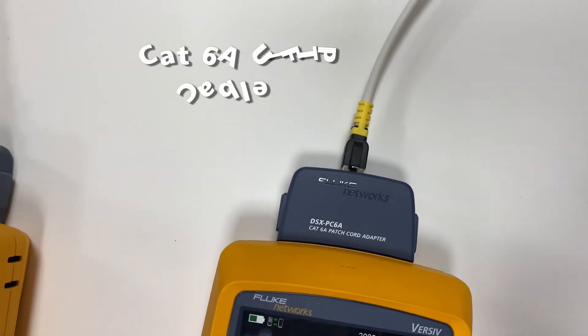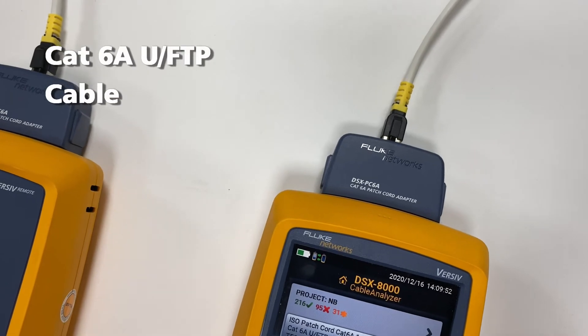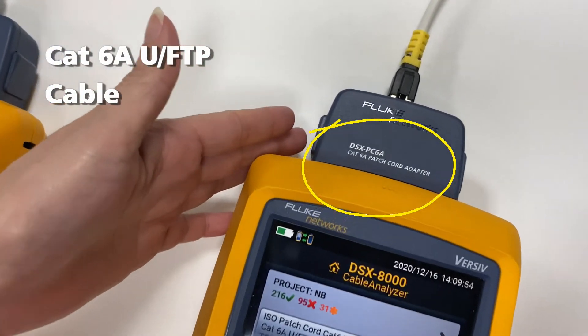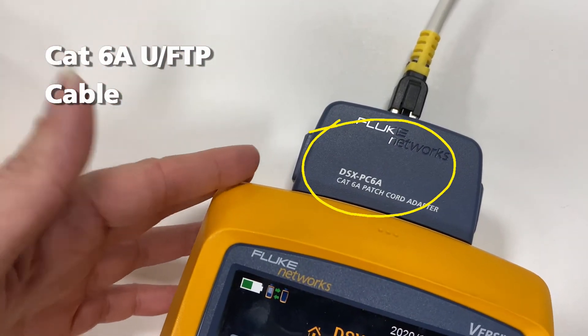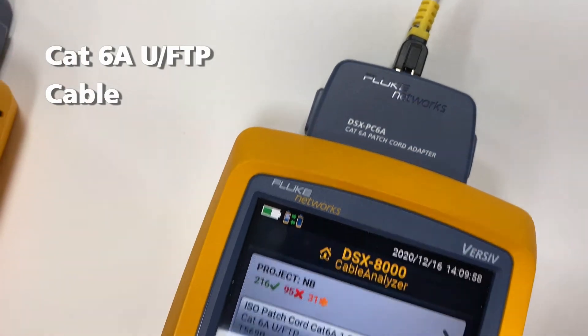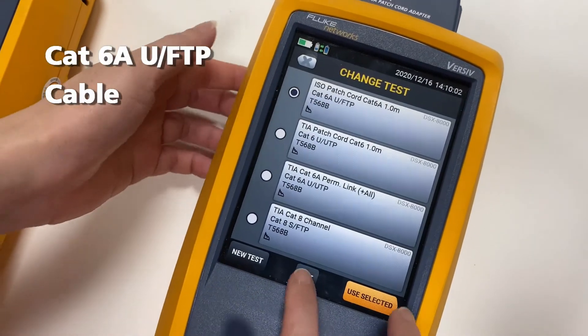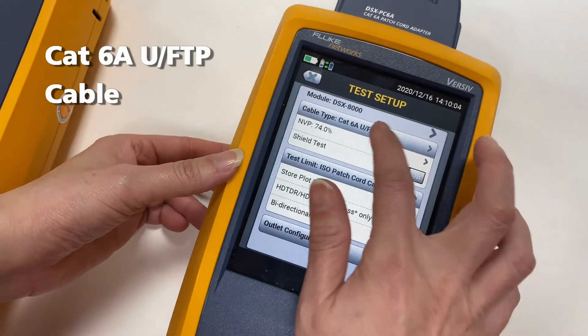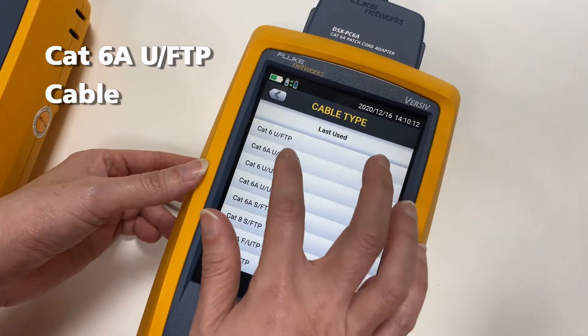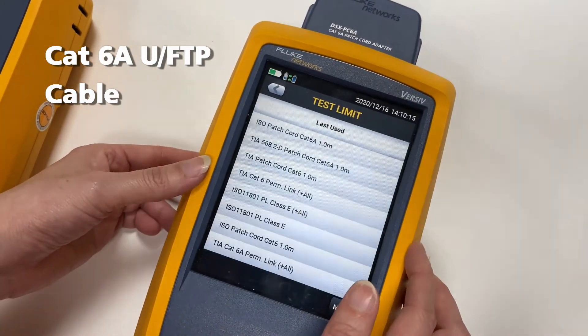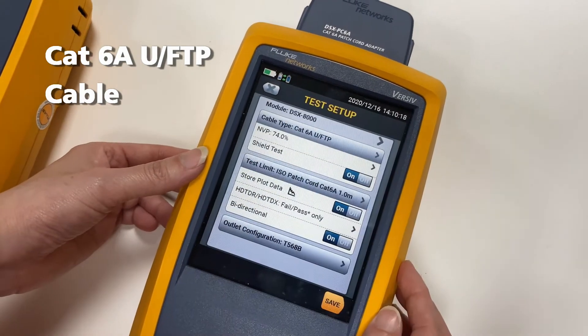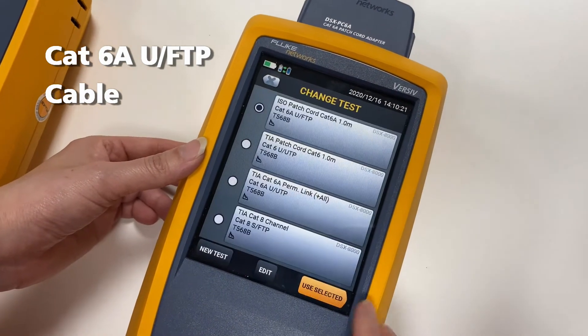Now we are going to demo the Cat6A U/FTP patch cord component test. First, please check the test adapter is correct for Cat6A. Then we are going to set up the cable — choose the cable by Cat6A U/FTP cable, and for test standard choose ISO patch cord Cat6A.